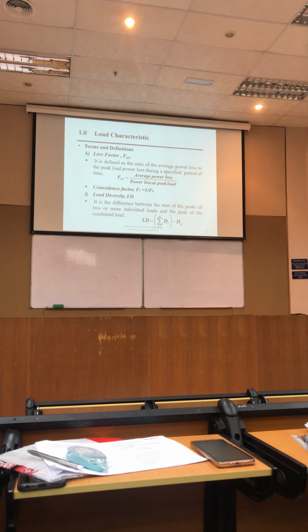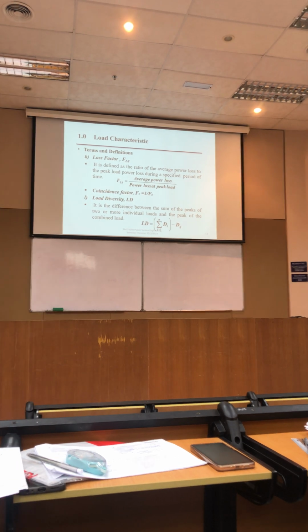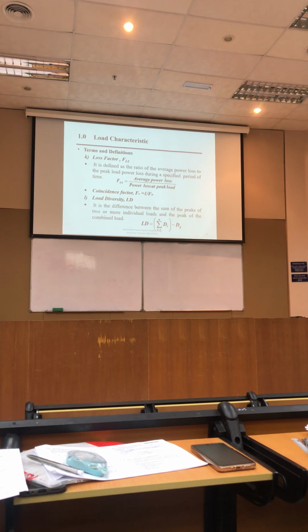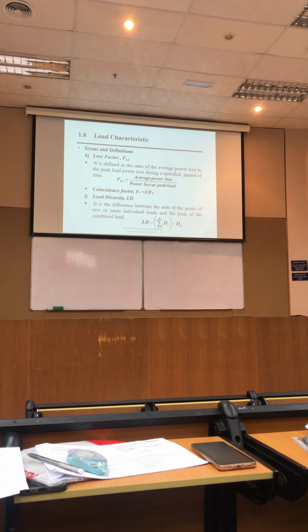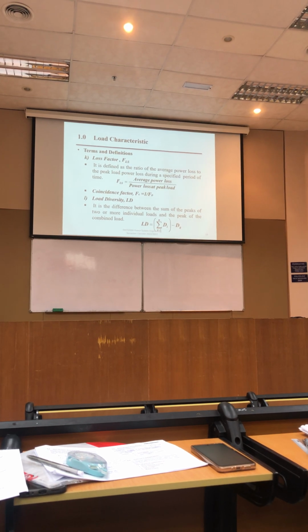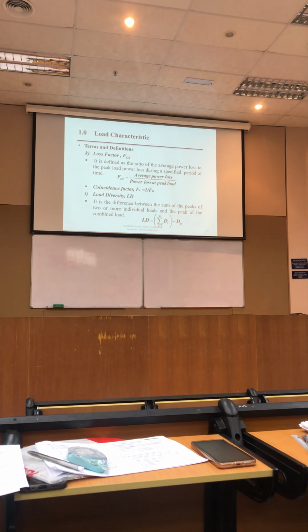We have also loss factor. We have to consider the loss. Is the ratio of the average power loss to the peak load power loss during a specified period of time. So average power loss divided by the power loss at peak load.